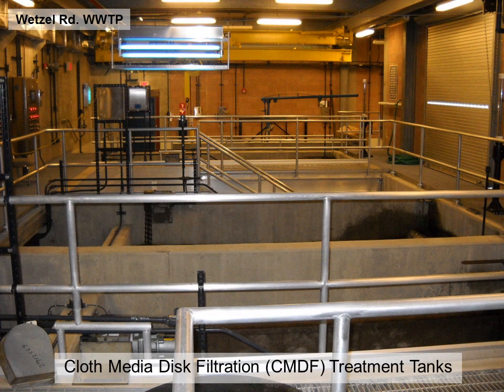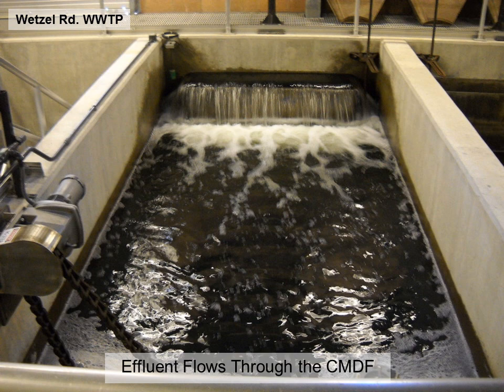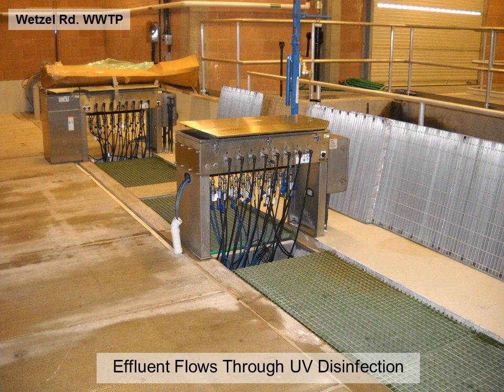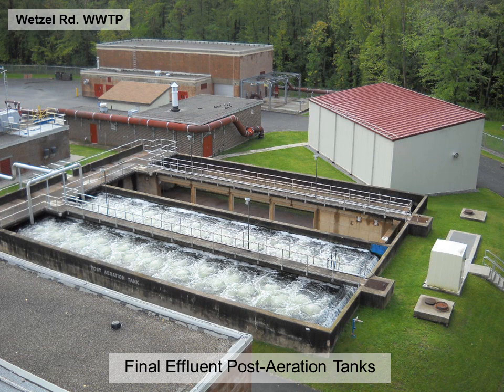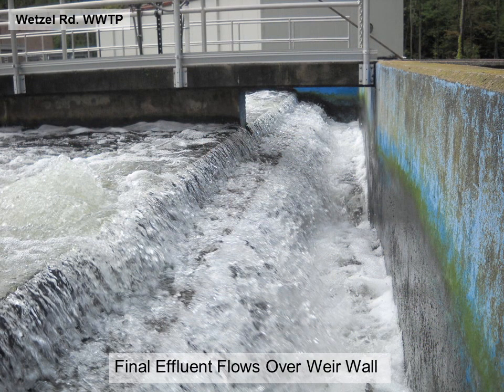Effluent from the BAF tanks passes through cloth media disc filters to remove particulate solids. Disinfection of this effluent is achieved by using ultraviolet light. The post-aeration tank ensures that the final effluent has a high dissolved oxygen concentration. The final effluent is discharged to the Seneca River.